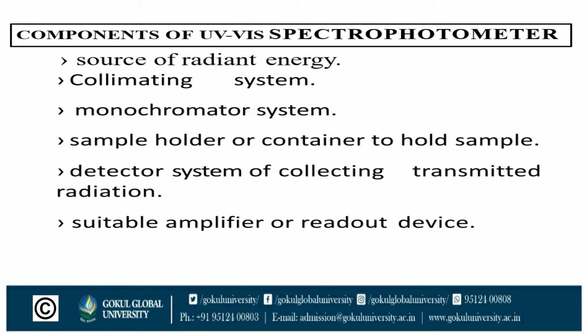Here is the list of components of the UV-visible spectrophotometer: the source of radiant energy, collimating system, monochromator system, sample holder or container to hold the sample, detector system for collecting transmitted radiation, and a suitable amplifier or readout device.